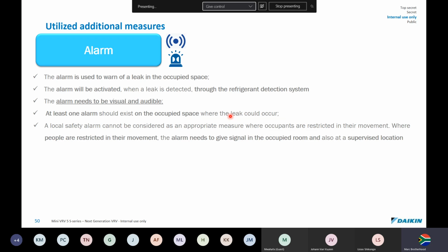So what are the alarms used for? The alarm is used to warn of a leak in the occupied space. Obviously, the alarm will be activated when a leak is detected through the refrigerant leak detection system. It's no good having this leak detection system if it can't be visual and audible, which is what I've said. We've incorporated an alarm as well as a red ring that will come on the remote control. At least one alarm should exist in the occupied space where the leak occurs.